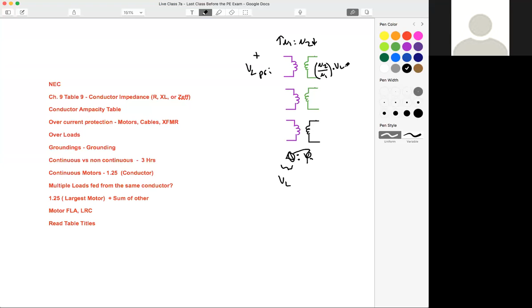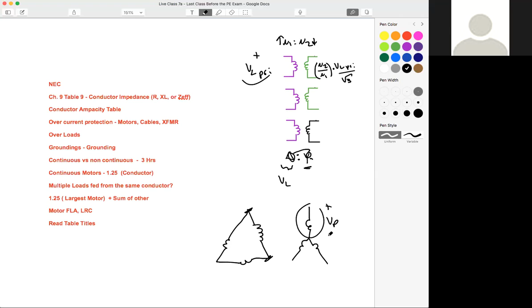And I want to say it also gets divided by the square root of 3, because here's our delta winding—check this, I need to verify that on that page. I'm trying to remember off the top of my head, but I believe for this configuration on the Y side, you'd also divide by the square root of 3, because we're essentially superimposing a line voltage value over our phase value. So this is phase voltage, but this is line voltage.